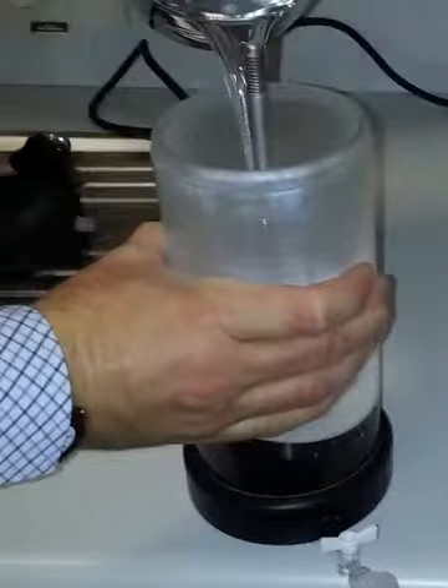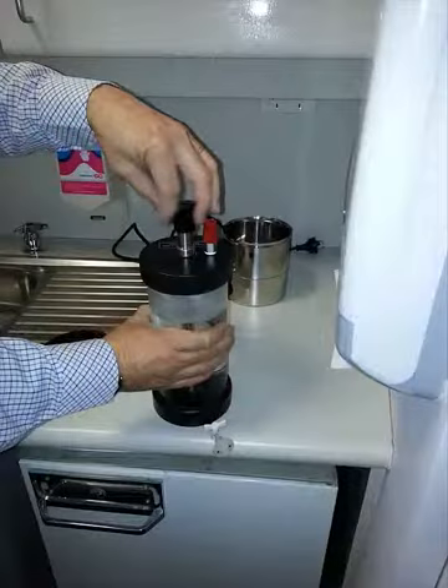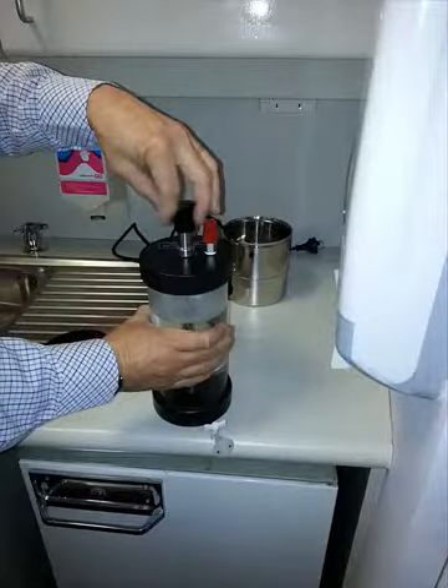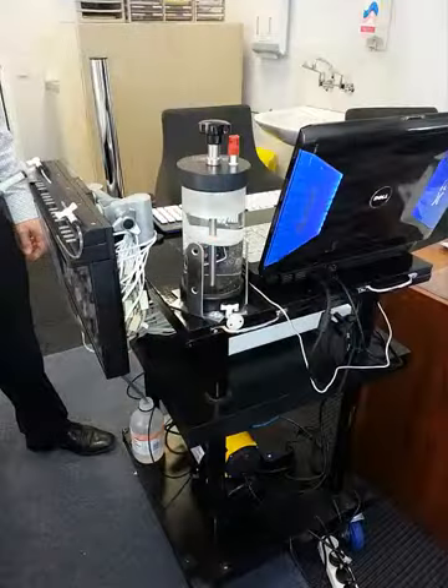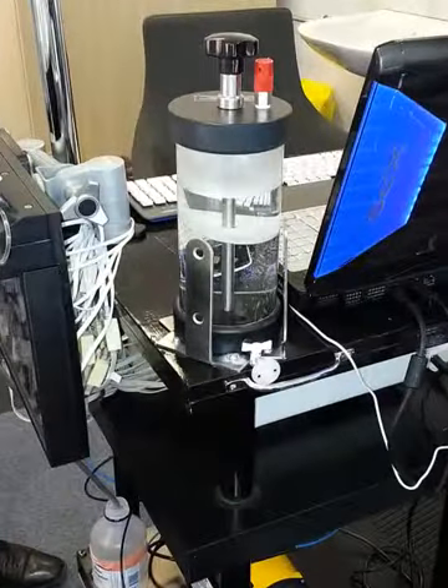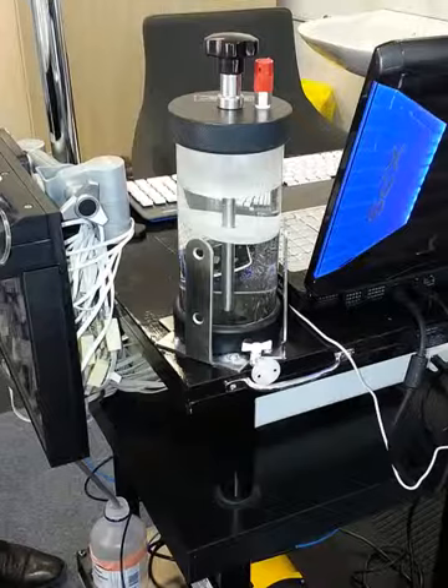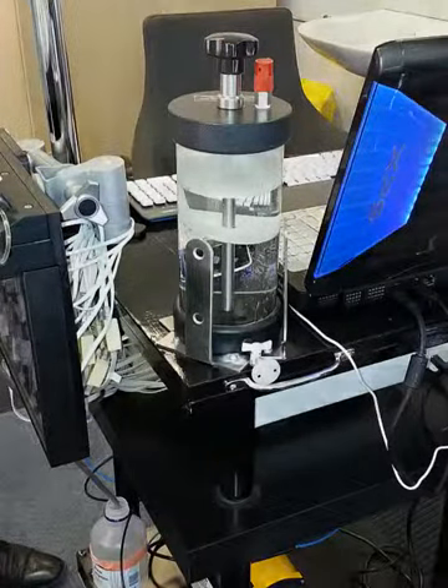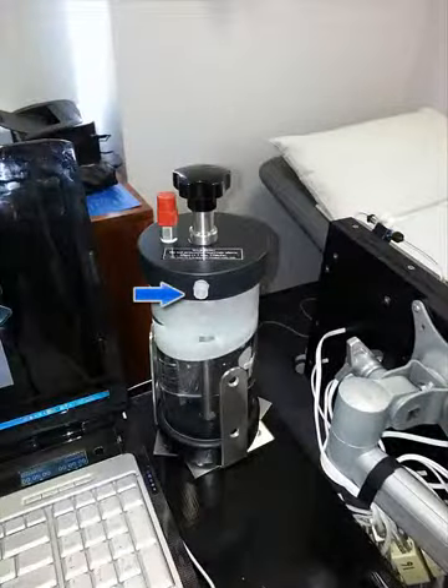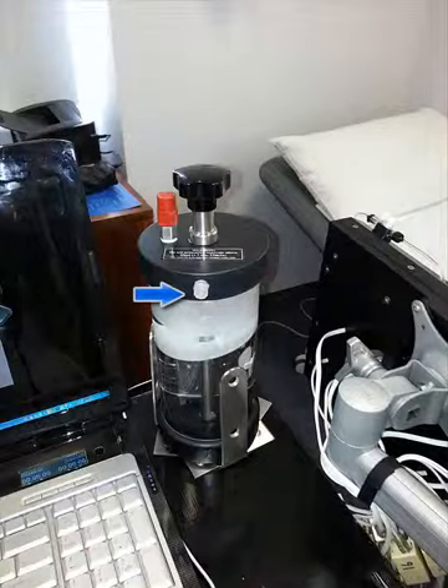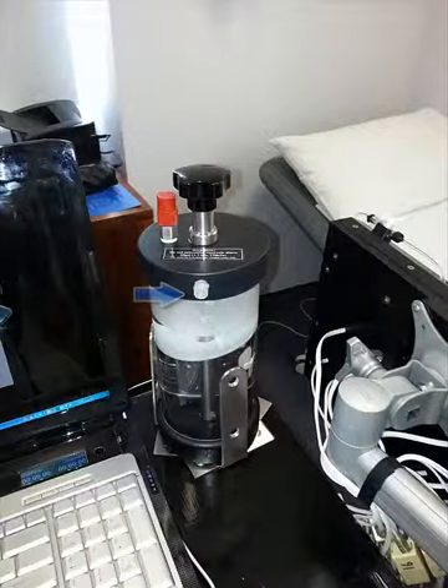Hold down the Perspex cylinder to maintain the seal, then screw the lid on the top firmly. Place the water reservoir back in its holder. Ensure that the water outlet is pointing away from the patient and important equipment, and that the air inlet is pointing in an appropriate direction for the blue air tubing to connect.